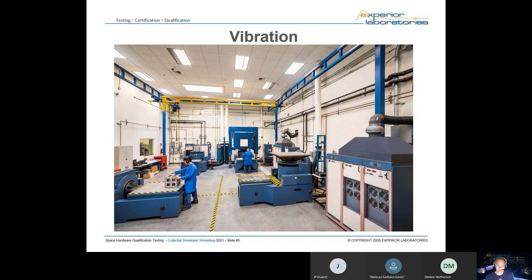On the vibration side, we have quite some capacity — that's why companies like JPL and NASA suppliers like Boeing come to us. We currently operate about 11 different vibration systems of many different sizes within our four buildings. They can handle anything from a very small sensor the size of your fingertip all the way to a full satellite of several thousand pounds, a rocket engine, or some other structure like lunar landers. That capacity and capability is why people seek us out.